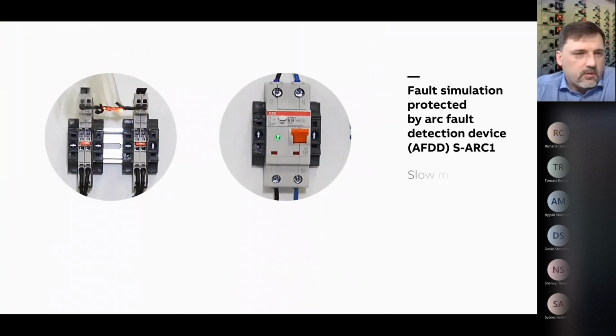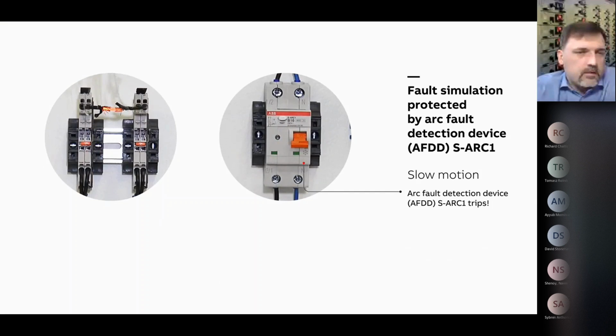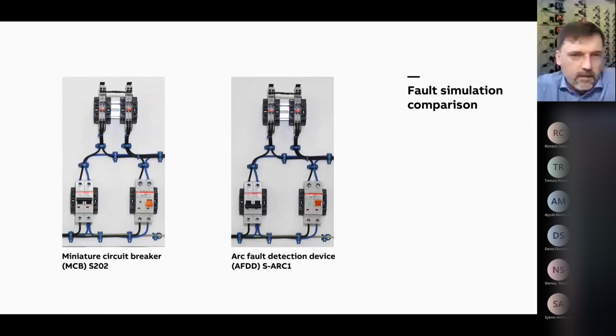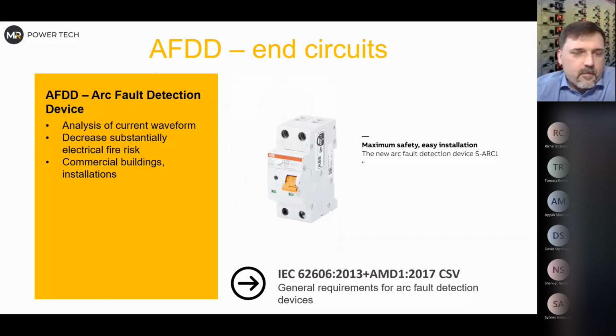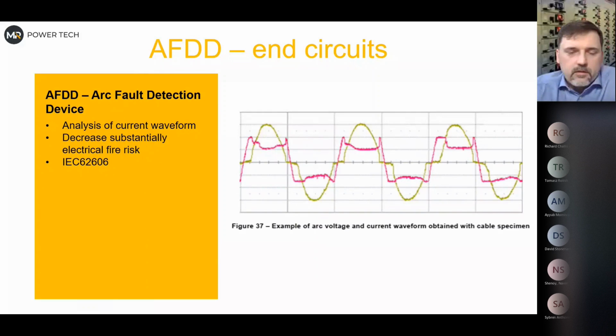So it has electronics inside that is monitoring the voltage and current, and it's trying to detect the disturbance that is correlated with the arc fault, with this arcing that's happening. Yeah, I think it's self-explanatory how it works. And I thought it would be nice to add it here just to give you an idea that this is on the end consumer unit level, which is very interesting from a fire prevention point of view. And again, as I said, it's not just an electromechanical device. There is electronics inside monitoring and actually trying to verify if we have an arc flash or if we start a drill or a motor. So it is very good at doing this.